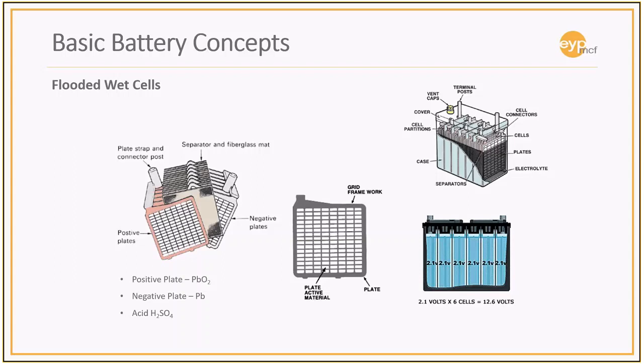Typically each cell is good for about 2.2 volts, based on an N cell voltage. So a fully operating battery is about 2.2 volts. When a battery is discharged, it could be at 1.67, or 1.65, or 1.63 volts per cell. In a UPS system, you add up all those voltages, and that's how you get to your float voltage on your UPS system.